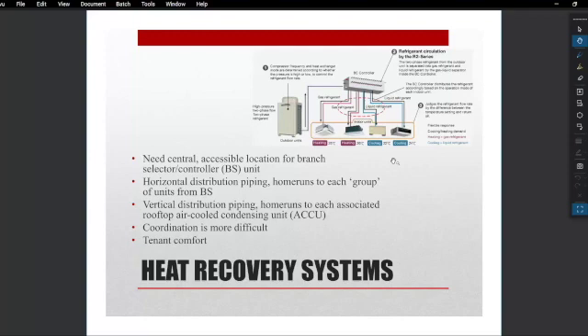So coordination is a little more difficult because in our case at Cornell, we have vertical refrigerant risers that stub down and penetrate out of the shaft to feed the branch controller and then distribute horizontally there. So we have a little bit of coordination with both vertical and horizontal refrigerant piping. And the horizontal, crossing the corridors, you have to fire rate that. You have to consider all of those things during coordination. And with the thickness of the insulation on these pipes, you're dealing with 3-inch pipes for every one, even though the lines are rather small themselves. But with the insulation, it actually takes up a lot of space coordination wise. But overall, you're not going to get the tenant complaints or those system shutdown problems that you would with a single mode system.